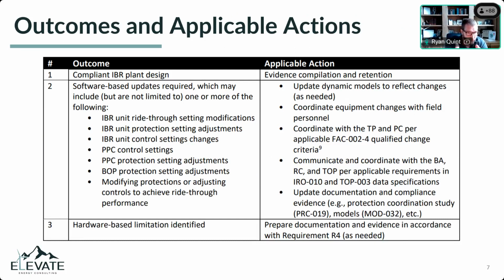Or you have software-based updates that are needed, which could be a slew of things - ride-through setting changes, protection setting changes, controller setting changes at the IBR units. Maybe the PPC controls need adjustments, maybe the balance of plant relay settings need to be changed. Based on early experiences, this appears quite common.